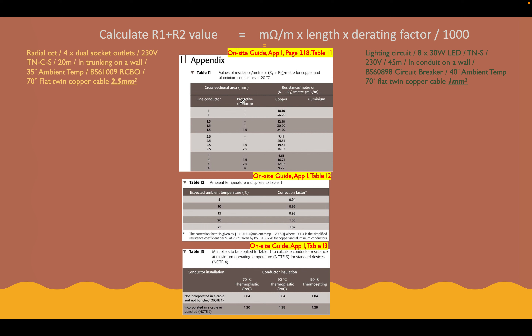These three tables are all from Appendix I in the on-site guide. You can see the references there highlighted in yellow. Note them down and get to know where they are. Table I1 is values of resistance per metre — the R1+R2 value per metre for copper and aluminium conductors at 20 degrees. That's the value it was tested at, so we need to bear that in mind. That's why we add a de-rating factor.